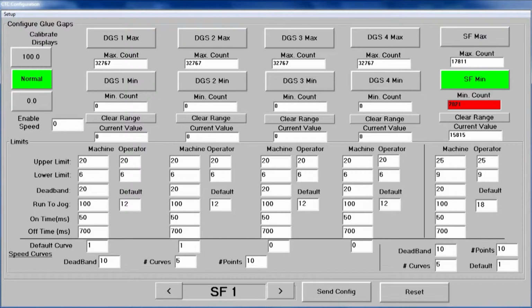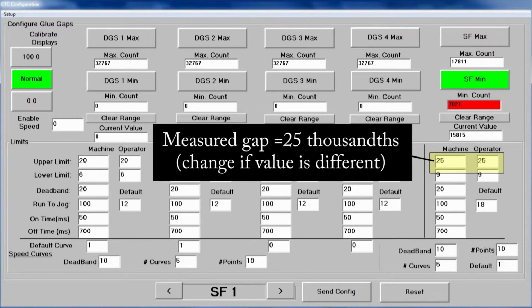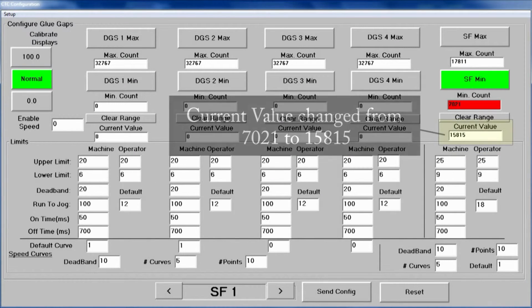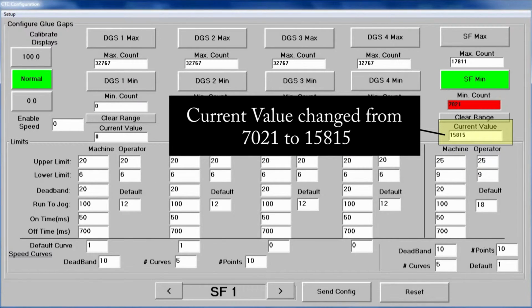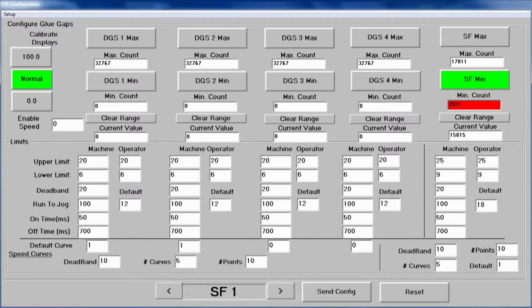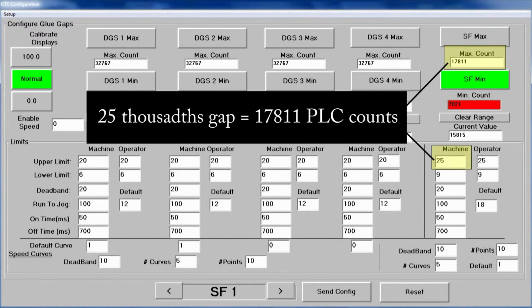We return to the Copar calibration screen and verify the machine and operator limit parameters are set at 25 thousandths. We note the current value field has increased since we have opened the gap to 25 thousandths. If the value did not change, maintenance should check for a broken position sensor. The upper limit gap value is directly related to the value in the SF max count field. Currently, the gap is at 25 thousandths when the max count field is 17,811.